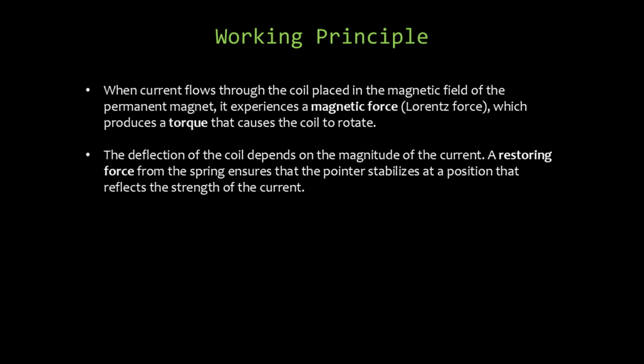The working principle of moving coil instruments is a beautiful demonstration of electromagnetic interaction. When electric current flows through the suspended coil within a permanent magnet's magnetic field, it experiences the Lorentz force, a magnetic force that generates a torque causing the coil to rotate. Think of it as a precise dance between electricity and magnetism, where current strength directly influences the pointer's movement. A restoring force from the spring ensures the pointer stabilizes at a position precisely reflecting the current's magnitude. This elegant mechanism transforms invisible electrical signals into visible, measurable movements.